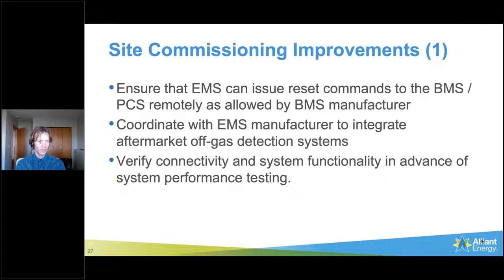We would also recommend coordinating with the EMS manufacturer, where possible, to integrate any aftermarket off-gas detection systems rather than rely on an integrator or in-house technical expertise. It seems obvious, but it's really important to verify connectivity and system functionality in advance of system performance testing, instead of just checking that the system looks available—running it through its paces in advance of testing, as much as you can control it.